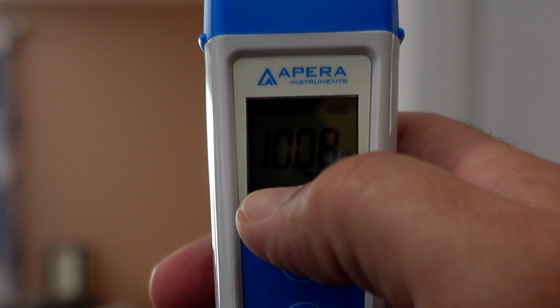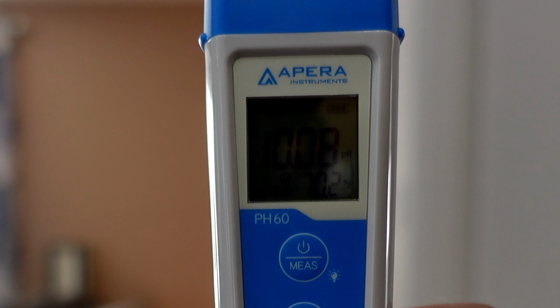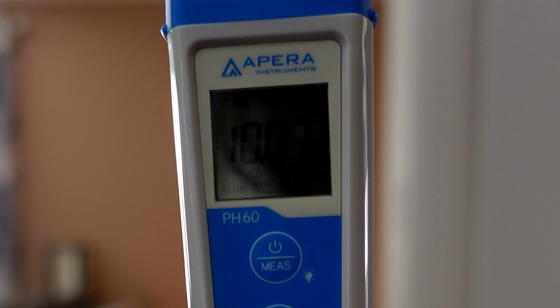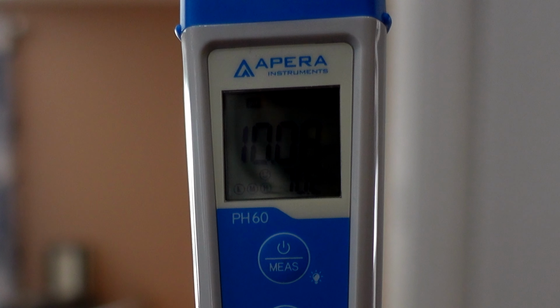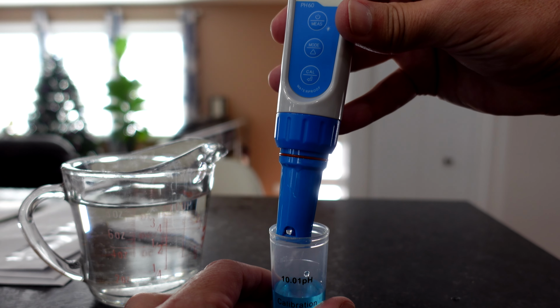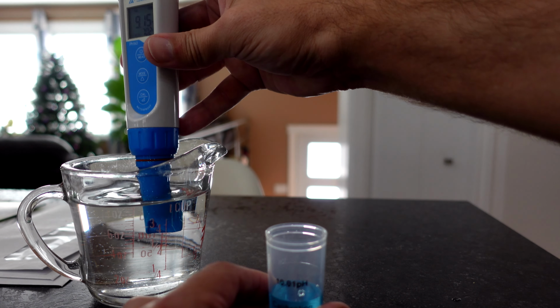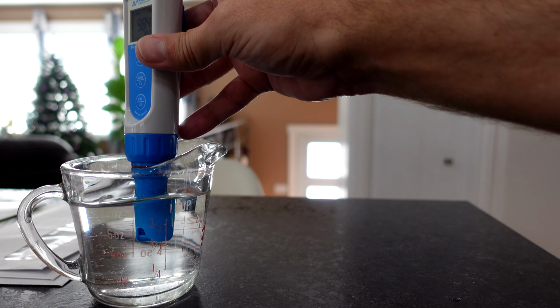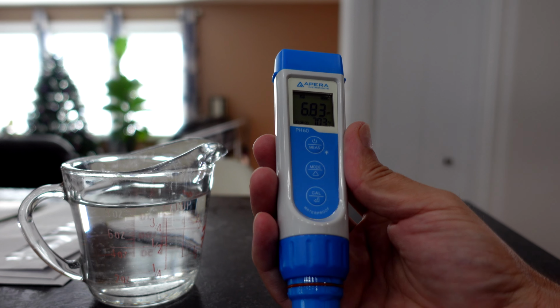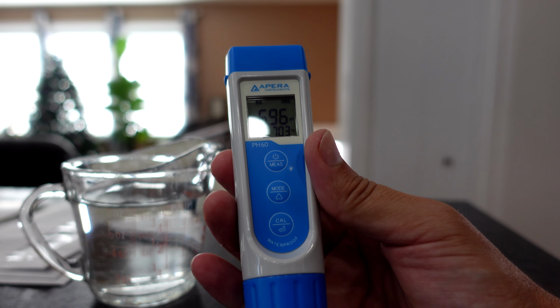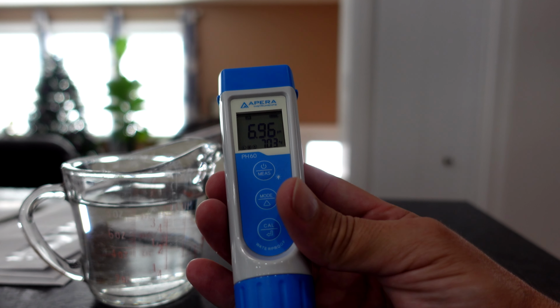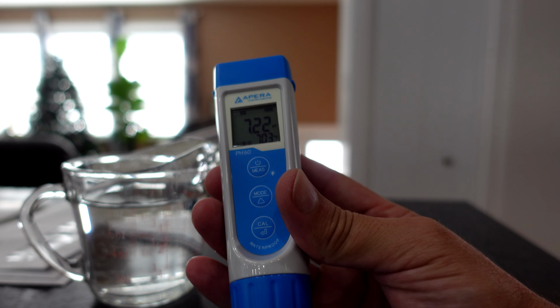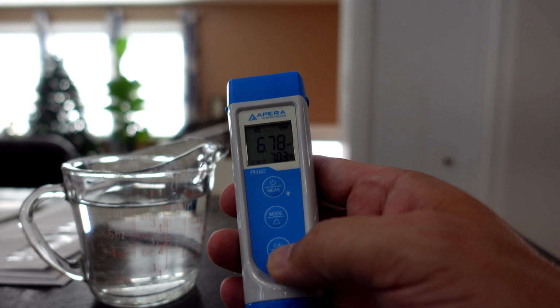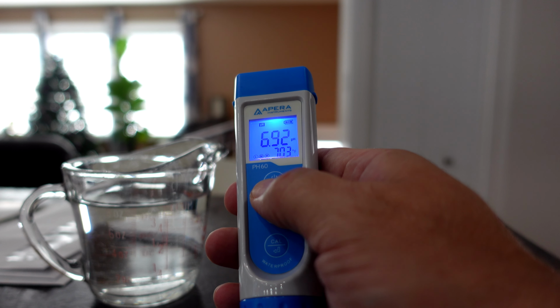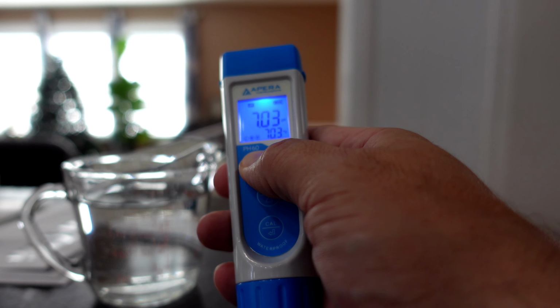Now you should see an L, M, and an H on your screen. That lets us know our calibration is complete. Here again, take the probe out, give it a rinse again. Our probe is now good for testing any pHs that we want. And if we want to, we can put it back into our storage, our KCl solution if we want to store it. And we can push and hold power to power off.